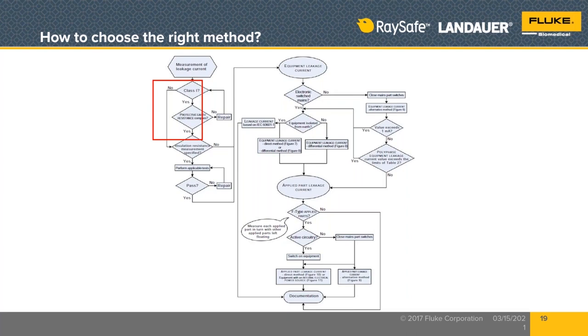All right, so typically it would have 3 connections on the power cord, and it will typically have an accessible ground, a ground test point that is usually on the back of the device, but not always. Sometimes it's somewhere else, but there will be an accessible ground. Now, there are newer medical devices called electrical safety class 1 that do not have this accessible ground test point. Just to let you know, there's another webinar that we have done that explains what to do when you don't have that accessible ground, even though it's supposed to be a class 1 device.